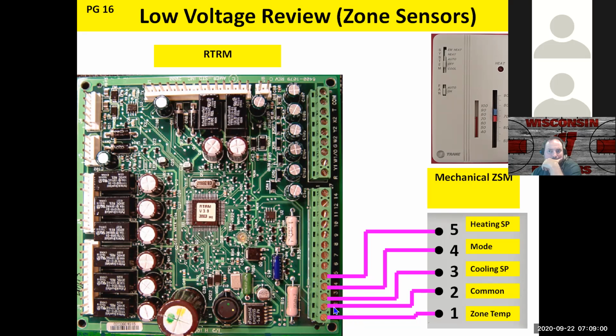1 and 2 is your zone temp, so you should be measuring probably about 2.5, 3 volts right here, if you're looking at the zone temperature. 2 is your common, and then 3 is going to be your cooling set point. 4 is your mode, which allows you to switch back and forth between heat and cool. And of course, 5 is going to be your heating set point.